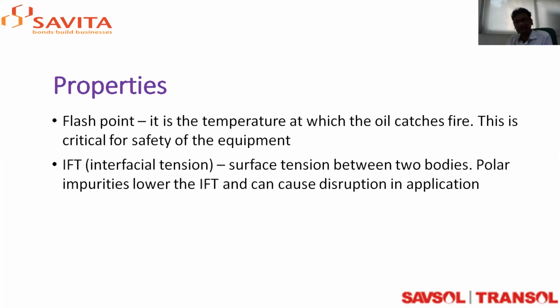These properties are very important because you should not have a lower flash point, since operating conditions of the transformer are around 80-90 degrees Celsius, and hotspot temperatures sometimes go near or even above the flash point. So you should choose a flash point that is well above the specification, as it will always be better for the manufacturer to have a certain safety cushion.